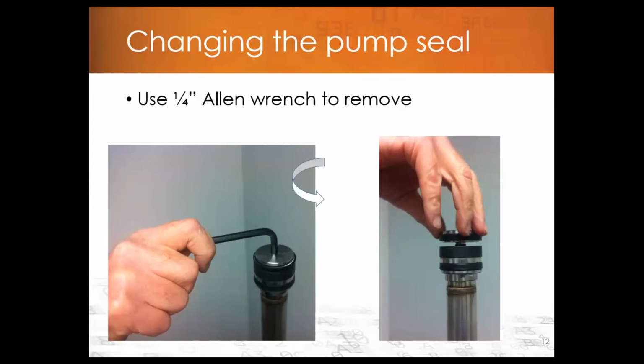Now in the photo, you'll see there you have the piston retainer with the piston seal on there. What's below there, that middle piece, is the wear ring, and it's made of bearing grade PEEK, and what that does is it keeps the piston centered when it's inside the cylinder and the piston is moving up and down. That wear ring keeps the piston centered. And then the item below there is the wiper seal. The wiper seal, as the name indicates, wipes the cylinder as the piston is moving up and down when you're running the pump.